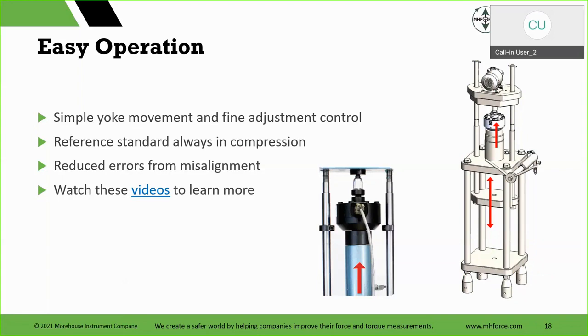And when I say really flat, that goes from one calibration to the next. After like the first year or two, with the right system, the load cell's drift is going to be very much minimized. And part of that is because we're only loading it in one direction. And then you have the rigidity of its design.